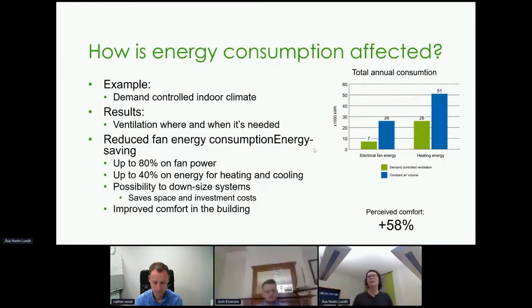If we look to the right, we have the system with constant air volume in blue, and in green we have demand-controlled ventilation. You can see it has a clear effect on energy consumption. You can save up to 80% on fan power and up to 40% on energy for heating and cooling. This means you might be able to downsize the system, saving space and investment cost, and you can also choose to improve comfort in the building.